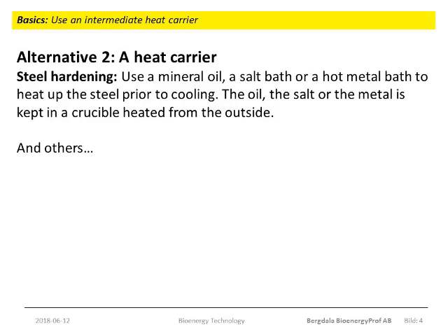If the fuel cannot be made clean enough, you may use an intermediate heating medium. In that case, you will have to have a heat exchanger in the system. The hot combustion products will then heat up the second medium, and the second medium will be in direct physical contact with the final product. The medium may then be selected not only to avoid a negative impact on the product, but may even be chosen to have a positive impact.